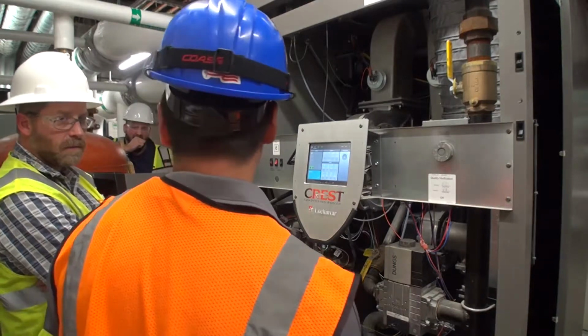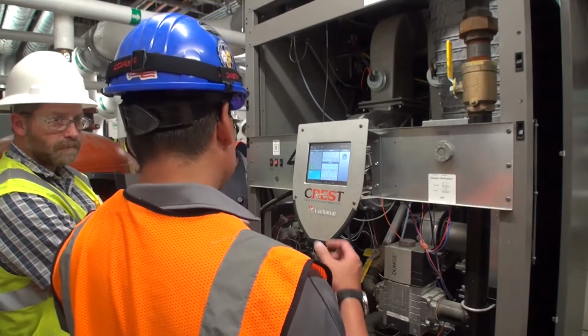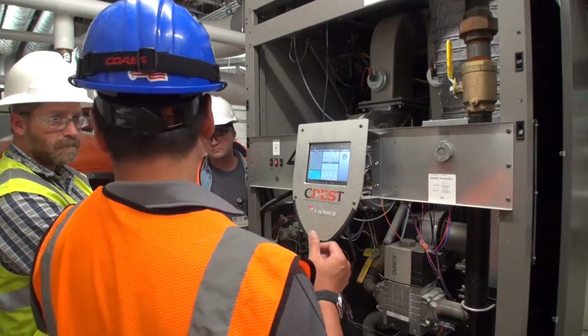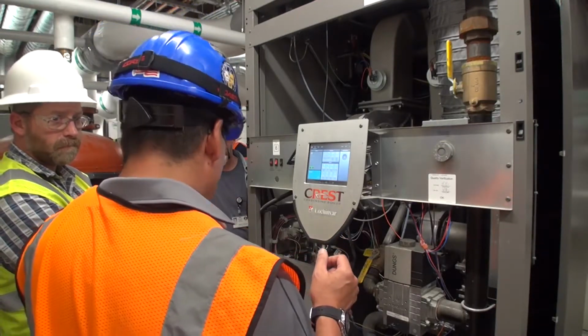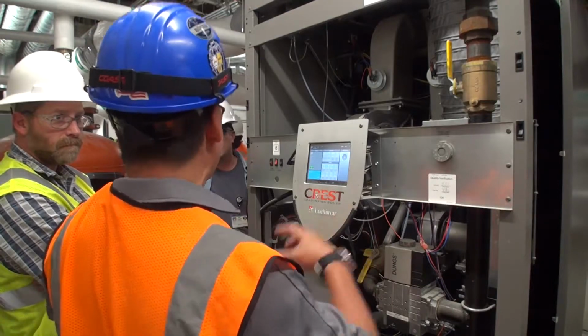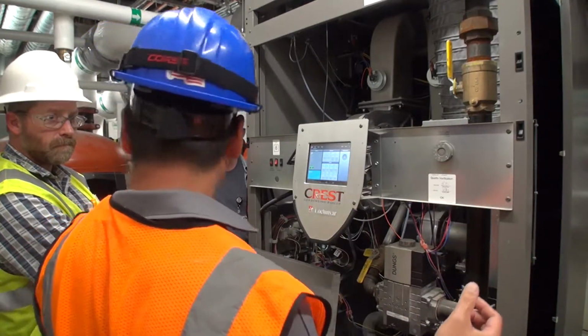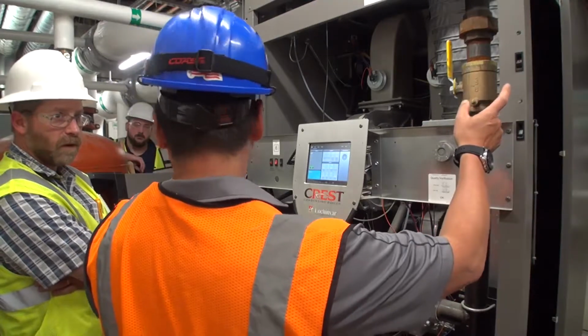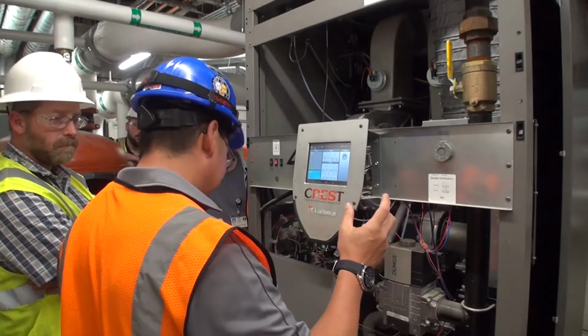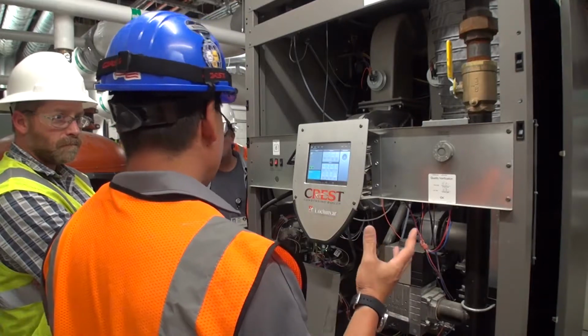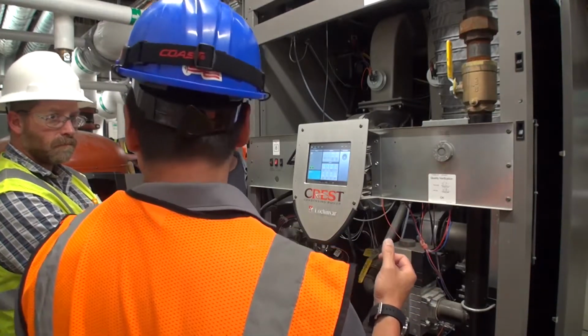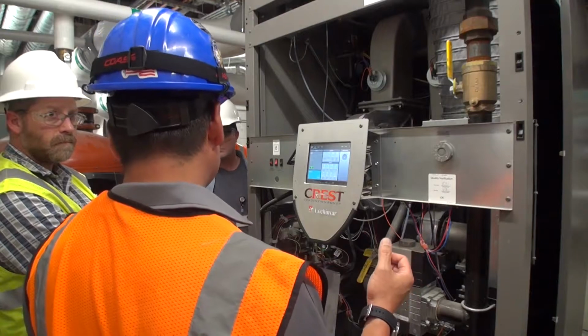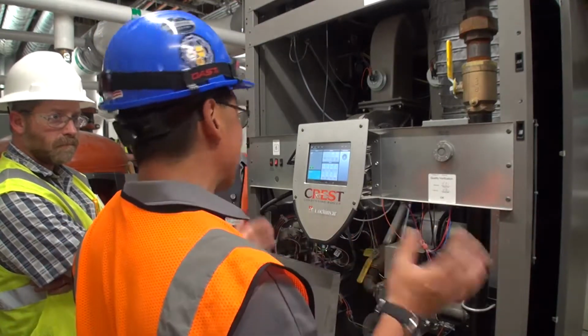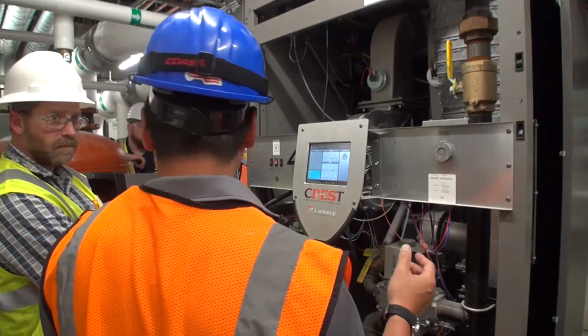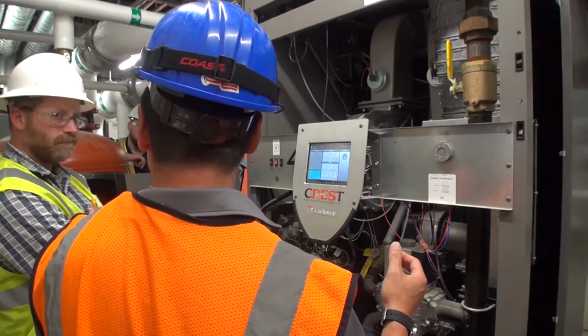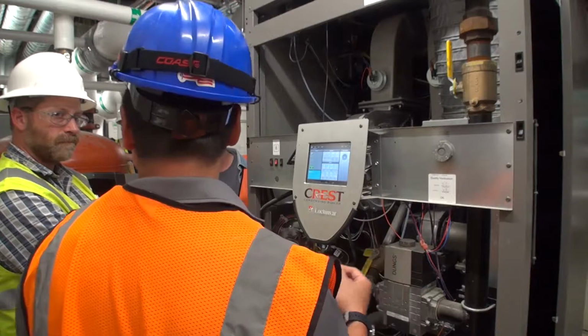No, because what you have at Fabian's is your system pumps in front of the boilers. Typically people put the system pumps after the boilers, so it's pushing water away from the boilers into the building. It's a negative draw away. So if you did anything to shut the boilers down, that wouldn't have stopped those pumps from running. The reason you're lifting the relief valves has nothing to do with the boilers. It was the pumps. The pumps are pushing into the boilers. They were deadheading the system. So the only way to stop that would be to kill the pumps.